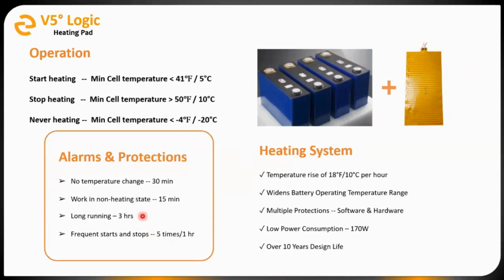Similarly, if the heating pad is running for 3 hours continuously, it'll turn off, and I think it's a 30-minute delay before it comes on and checks again. And then kind of the same logic here. If the BMS sees that the heating pad is starting and stopping frequently, so off, on, within a predetermined amount of time, it will give you an error as well. The heating pad operation can also be controlled using our PC software. So for troubleshooting and further testing, you can play around with it slightly.